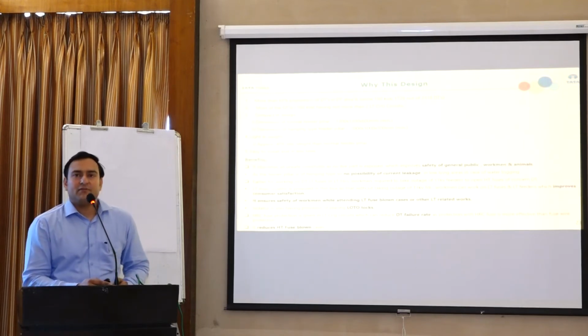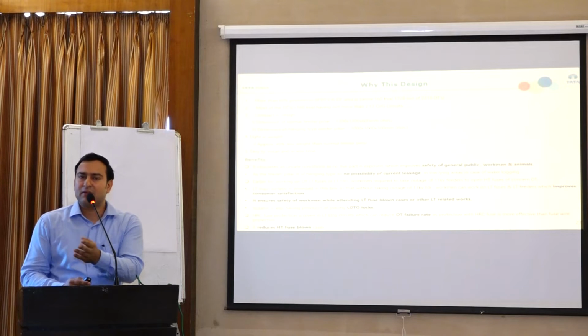This is the design detail - a hanging type feeder pillar. We found more than approximately 800 cases where the LT fuse system was totally open, with distribution open and overhead. This made the LT system easily accessible to people, stray animals, or street dogs, creating an easy electrocution point. There was also a challenge for linemen working on this open fuse system.